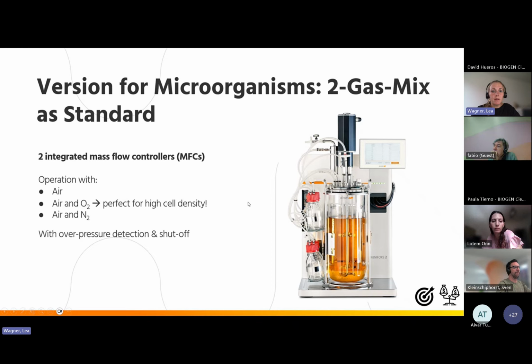And this is a very high standard because we have MFCs as standard. So most of the competitors just have rotameters and magnetic valves. But with the MFCs, the customers get more accurate results, and usually also during scale up, MFCs are used rather than just rotameters and magnetic valves. So this makes the scale up easier. And the gassing also has a safety feature, so there's overpressure detection and shutoff in case the exit gas filter blocks, for example.